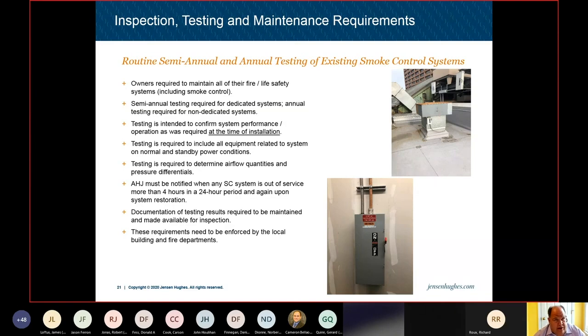That doesn't mean that the testing criteria can't change. So the testing, just like with NFPA 72, you might have a 20-year-old fire alarm system, but your testing needs to be in accordance with the most recently adopted NFPA 72 version for testing in your local jurisdiction. So same thing applies for smoke control.